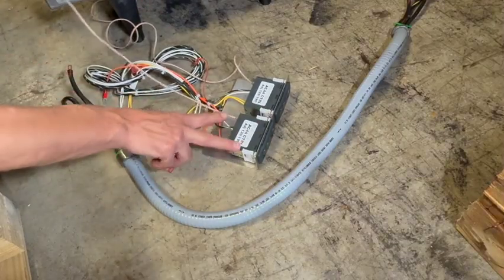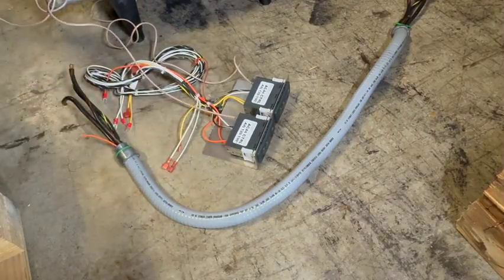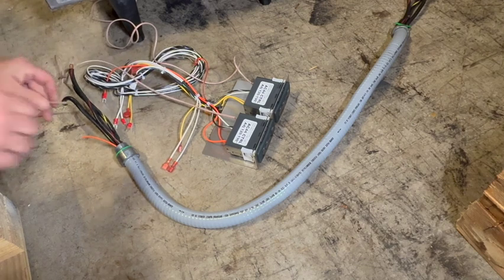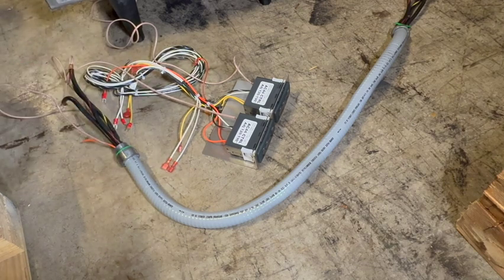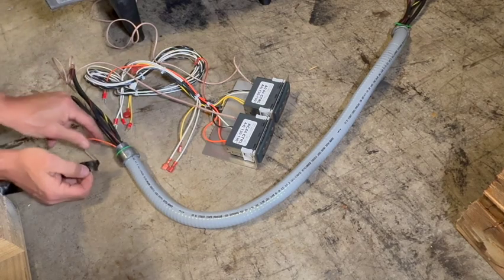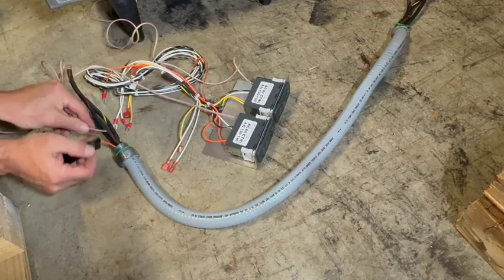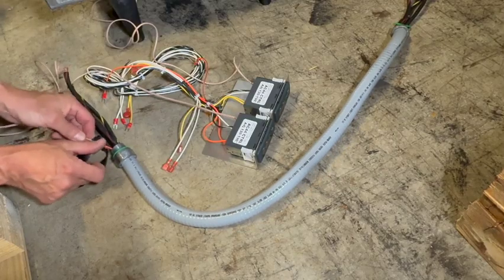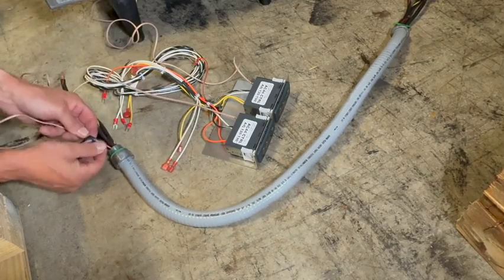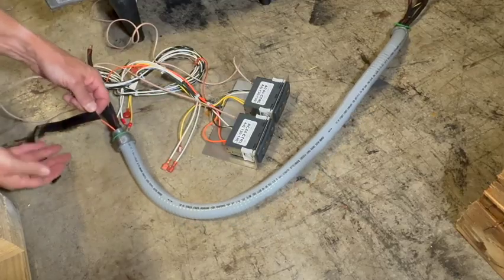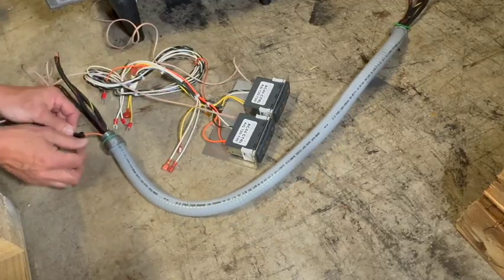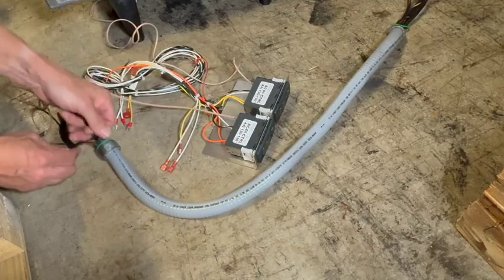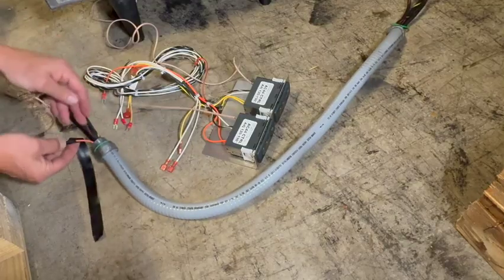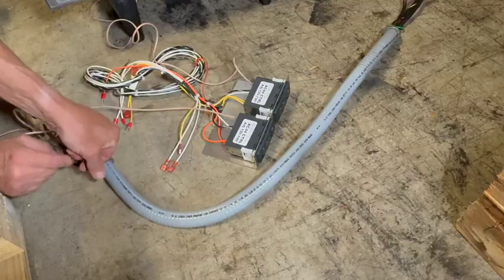So here's the process of me getting that probe wire through the conduit. Again, it was much easier doing it by pulling this conduit outside the machine, and so I can straighten up the wires. But basically you've got to use some electrical tape, tie in the probe to that orange wire, and then you're just going to pull that orange wire so that the probe wire comes out the other side of that conduit.